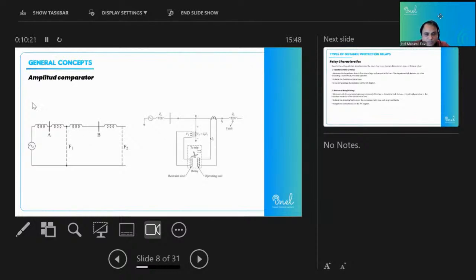And by this amplitude comparison, the relay will decide whether it is a fault or an abnormal operating condition or overloading condition. So this is basically the concept of the amplitude comparator. We compare two quantities: one is the actual impedance, whose values we put in the relay, and the other is an operational impedance which the relay calculates every moment. There is a current and voltage on the transmission line, and it will compare. On the basis of this comparison, it will make some decisions. There may be some conditions, which we will discuss later, where the impedance is less than that value but still there is no fault. There are some situations, but these are exceptions. We will discuss later.